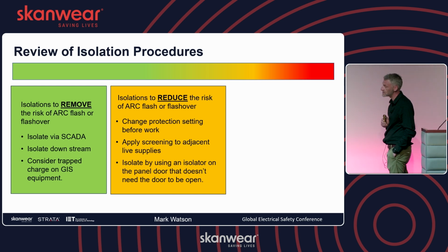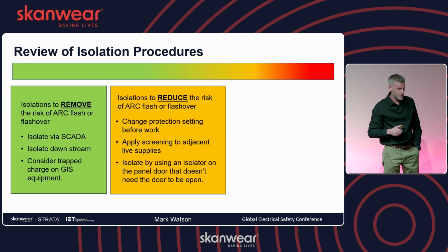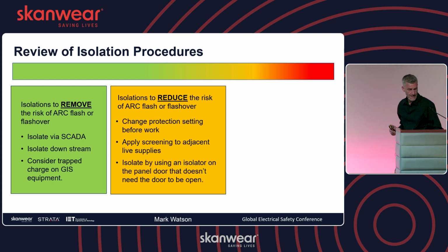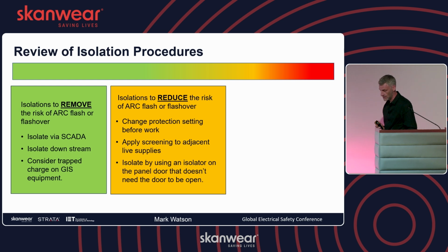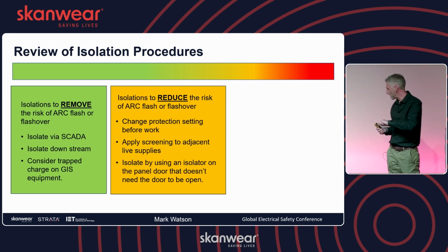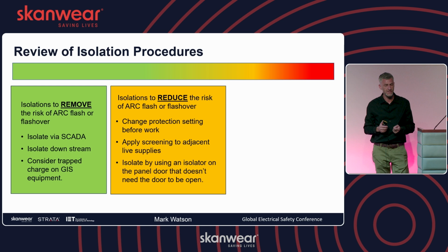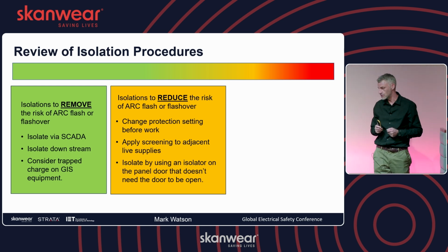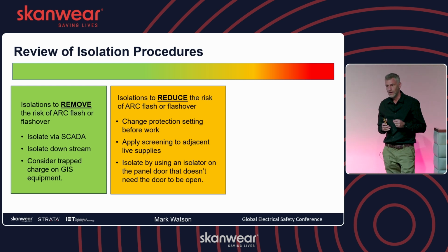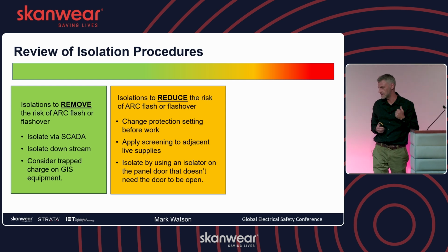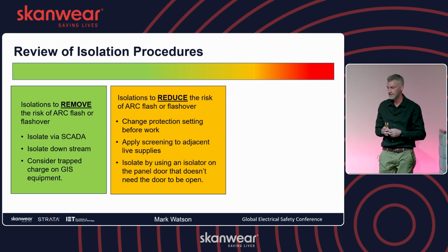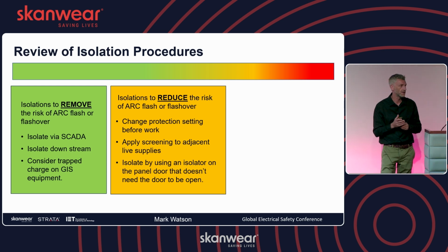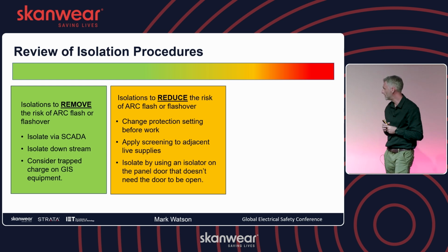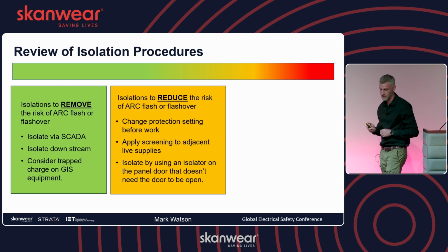Change protection settings, apply screening adjacent to live equipment. We talked about changing the protection settings - some relays have a maintenance mode, some have normal operations. Again, consider how you control that, like Jennie said. It's okay applying a maintenance mode, but the last thing you want to do is get off the turbine or leave a substation in a hurry and leave it in that position. Something small operates, and next thing you know you've tripped your HV system - it's a bigger problem then. So make sure that's detailed in a process for how to remember to put it back.